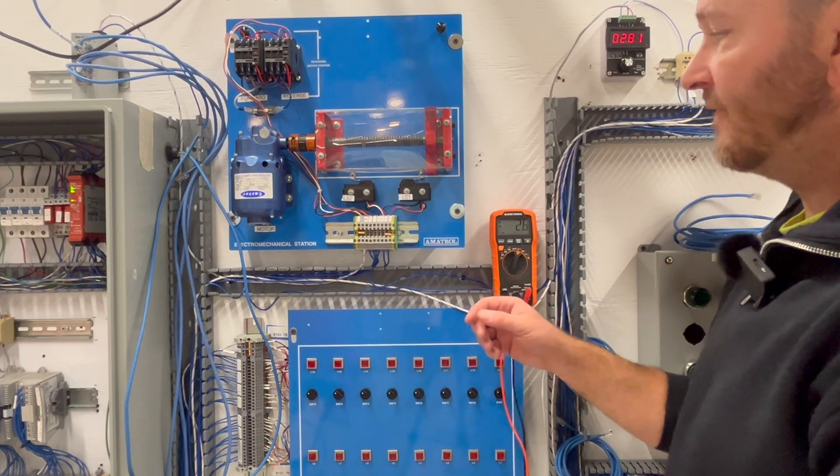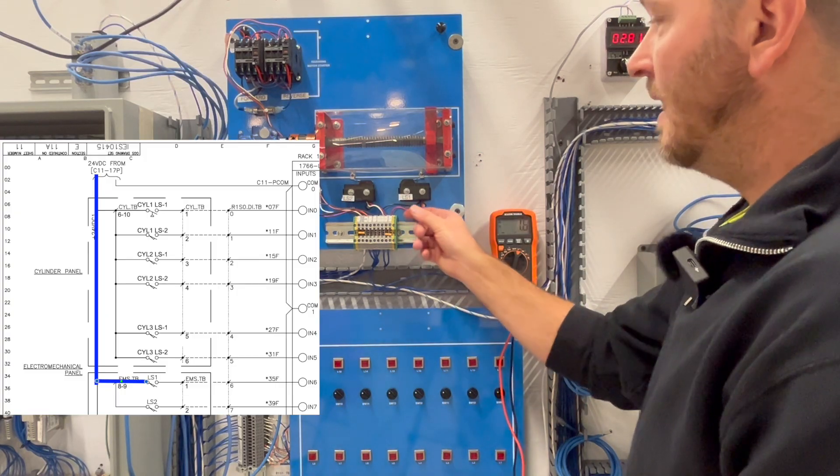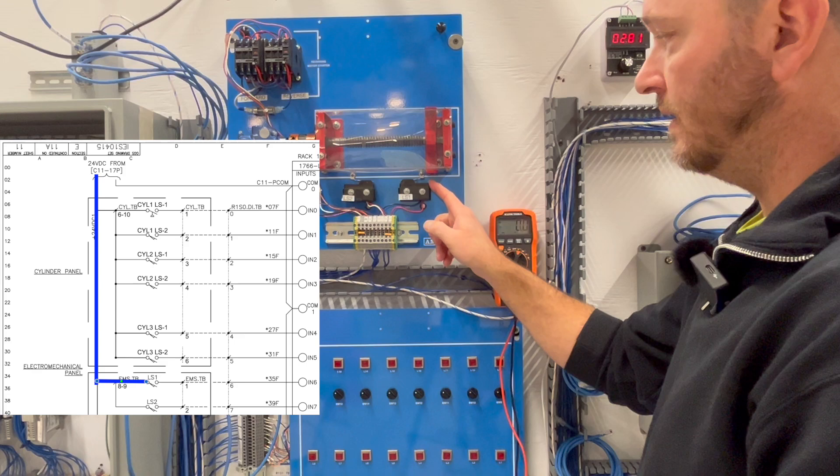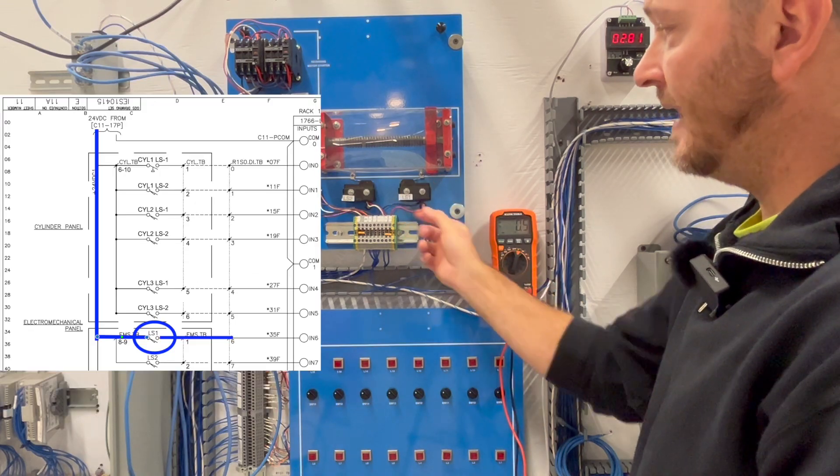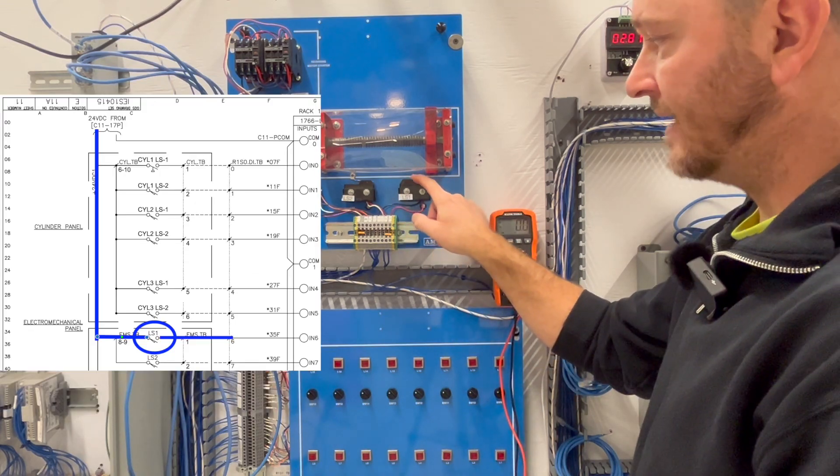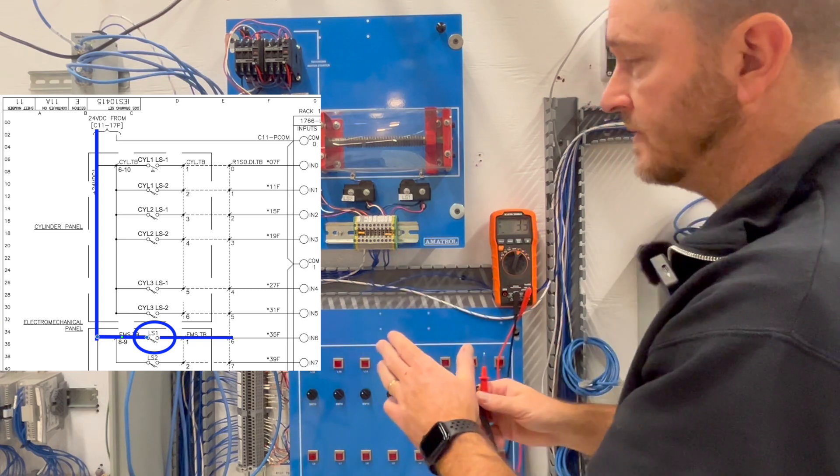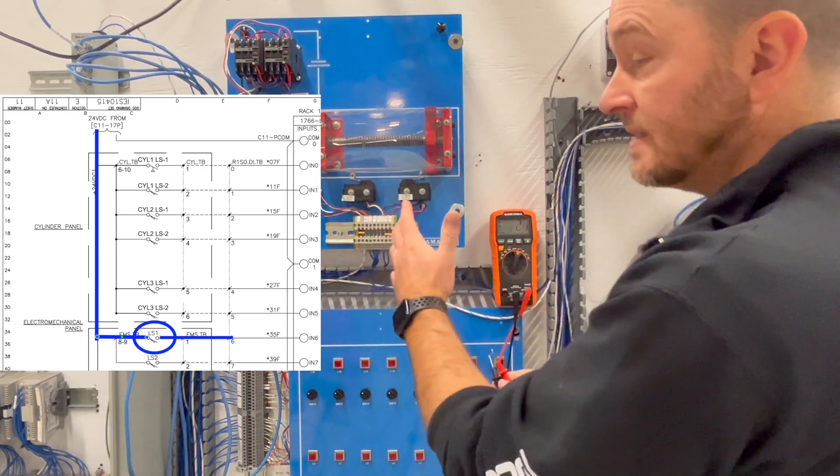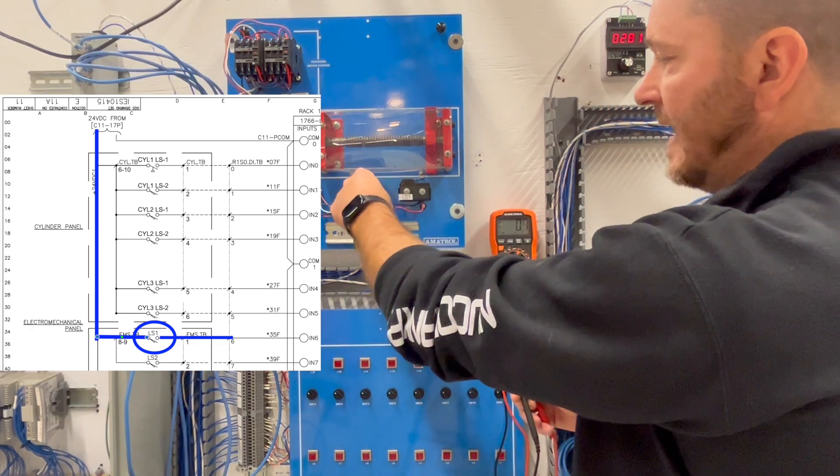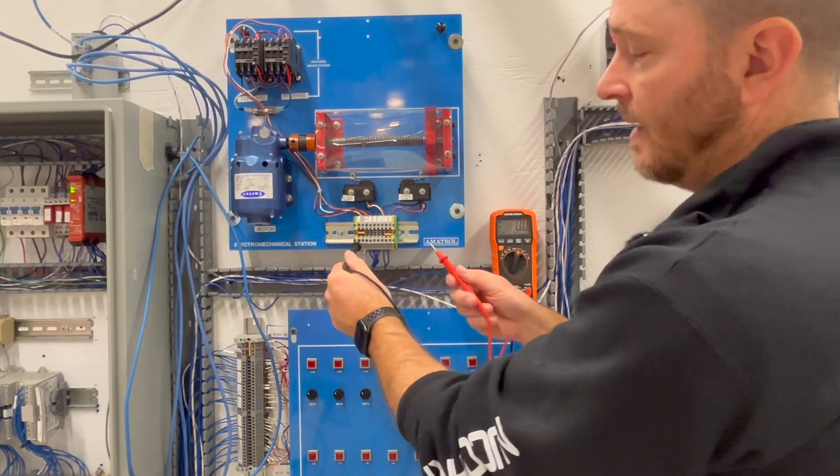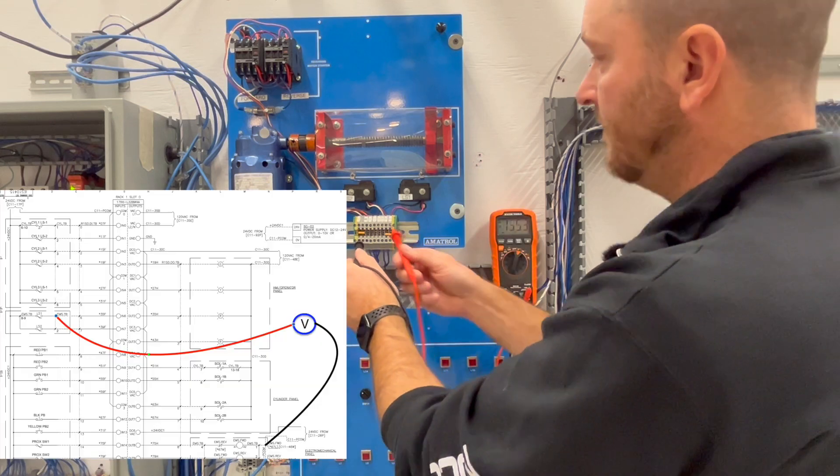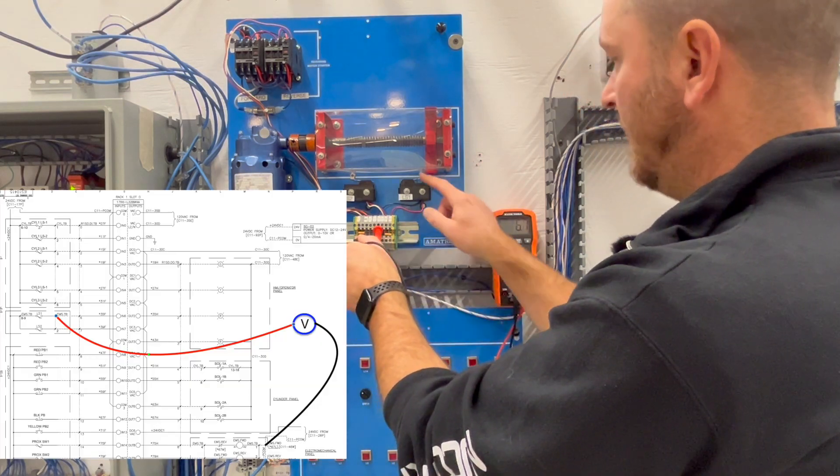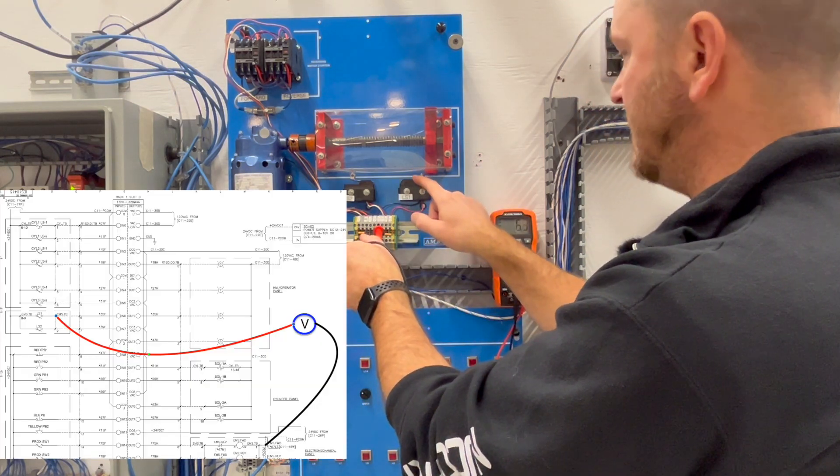Now if I look at the schematic diagram I have a hotline coming up to here and then a hotline coming out when this is activated. Okay so you can see on the schematic diagram this is wired to number six and in this case I'm really lucky I can trace that line right to here. So I'm going to come over here from my common into six and I'm going to activate this to see if I'm getting voltage.